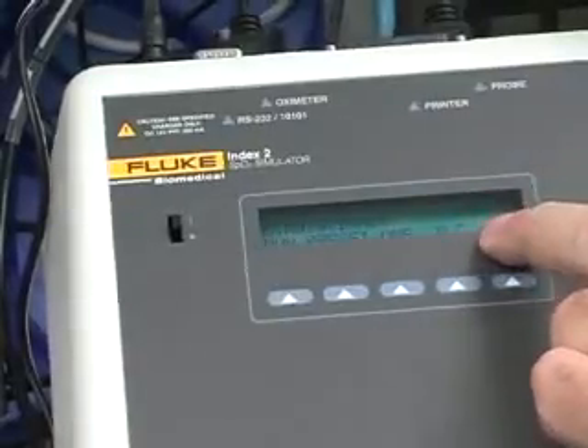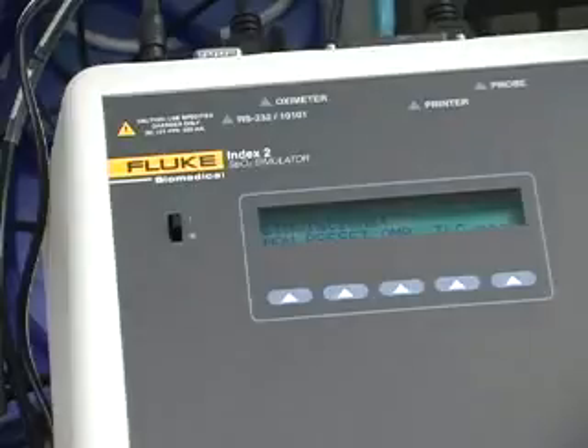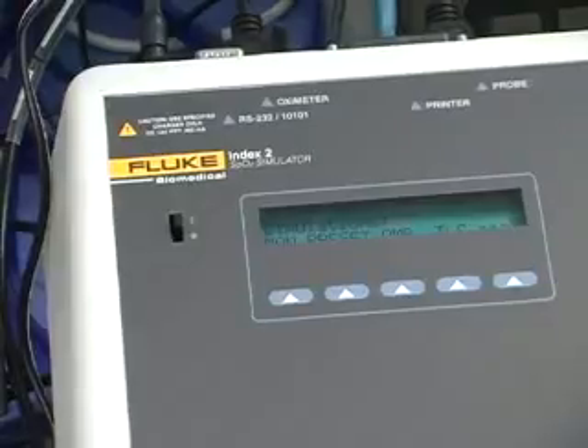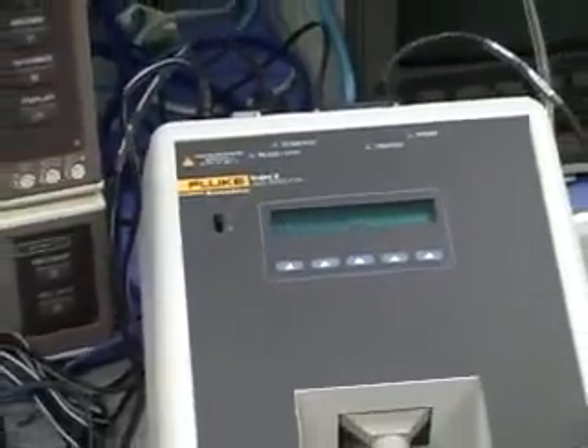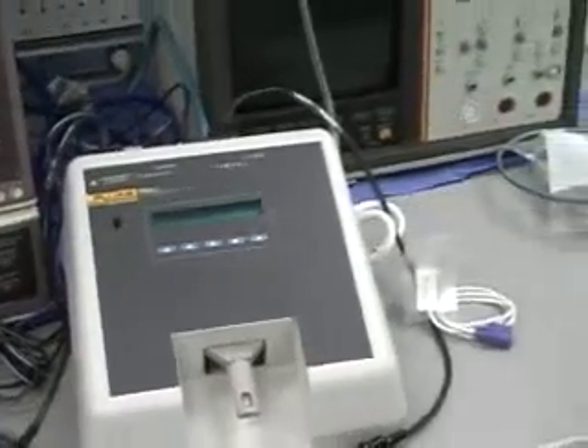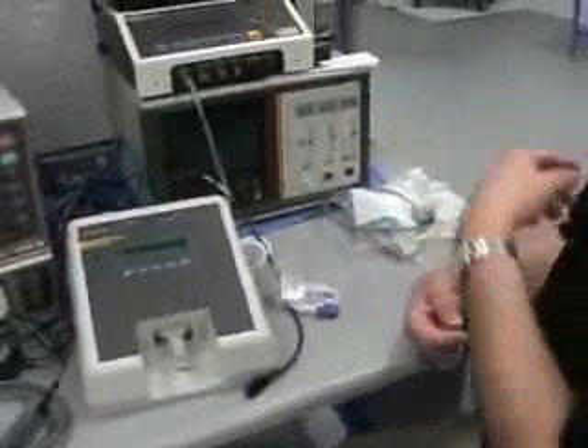We're not going to really mess with the TLC at this point. In upcoming versions of this, that's being redone, so you won't have to really mess with it. The TLC is basically a transmission level control or light control. I've heard it called both, but it's a level control, and that sets the DC operating points of both the visible red and the infrared. But it does them both at the same time. Now, if you wanted to change these a little differently for each of the colors, you couldn't do that. So the earlier versions of this, in the M version, had that capability. You could independently set the infrared light levels and also the DC levels, infrared and visible red, which is what you really need to have. So we're reverting back to the old method. It's much better.